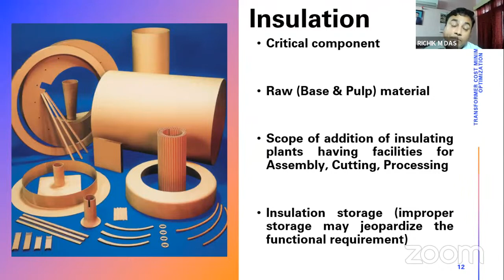Because for large rating transformers, if you see the CTU rolling plan up to 27-28, many transformers and reactors are required. To cope with this demand, manufacturers should take such initiatives, and then they can have the transformers available in time. Then insulation storage. This item is very critical and there is a lot of risk involved. How? If we have moisture or contamination, the functional requirement of the insulation will be jeopardized. So we should have good storage of the insulation.